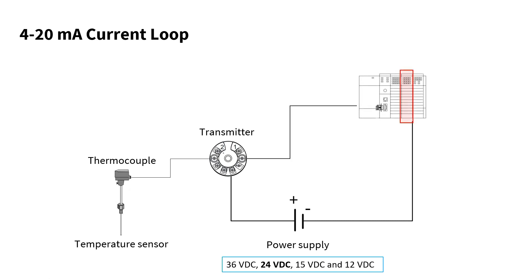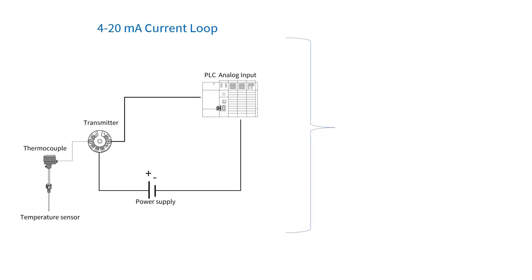Finally, a receiver reads the current loop — in this example I have an analog input module. The reading gets measured from the thermocouple, the transmitter converts that to current, and then we can read that using the PLC analog input. Each element in the loop has a voltage drop, but because we're using the 4 to 20 milliamps current loop, the current produced by the transmitter remains the same throughout the loop.